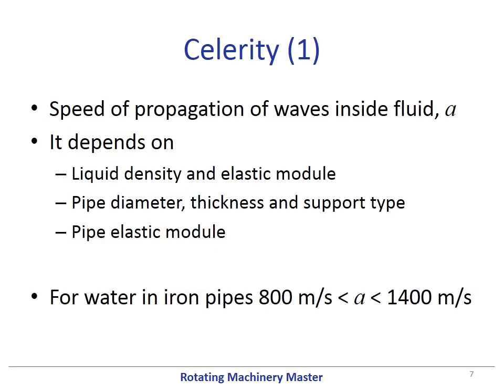The speed of propagation of waves inside a fluid is also called celerity. It depends on the liquid density and its elastic modulus, the pipe diameter, thickness and support type, and the pipe elastic modulus. For example, for water in iron pipes it is something between 800 meters per second and 1400 meters per second, depending on the pipe characteristics.